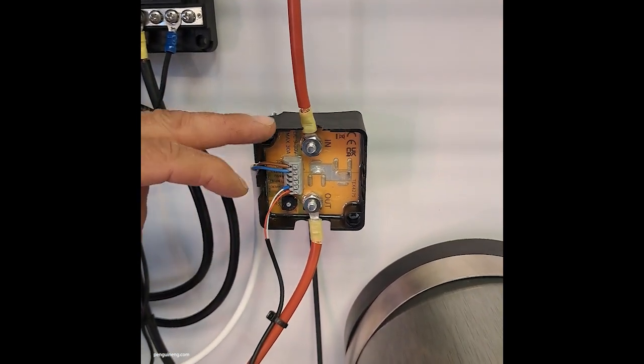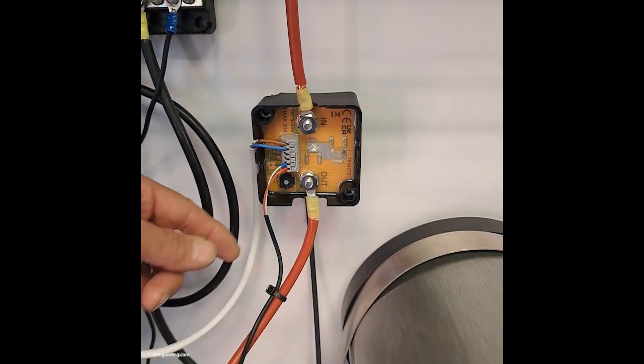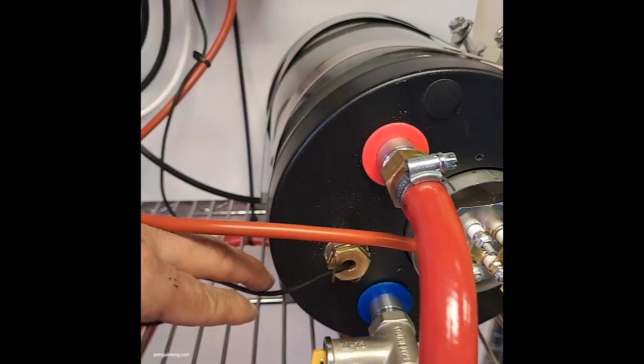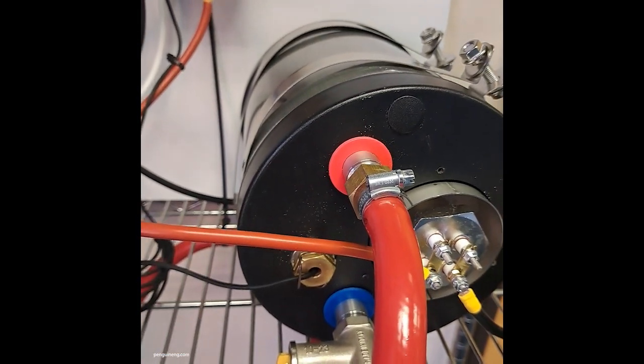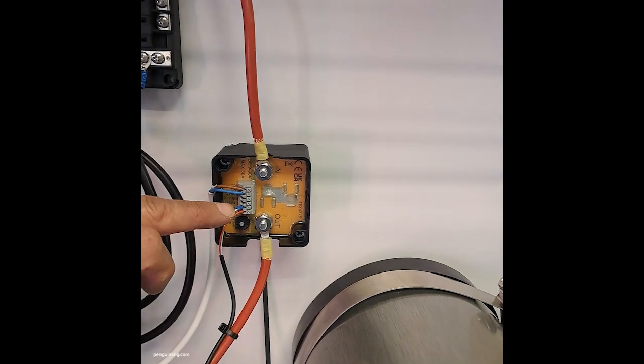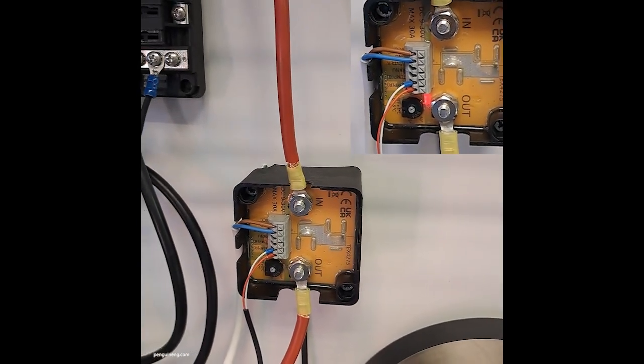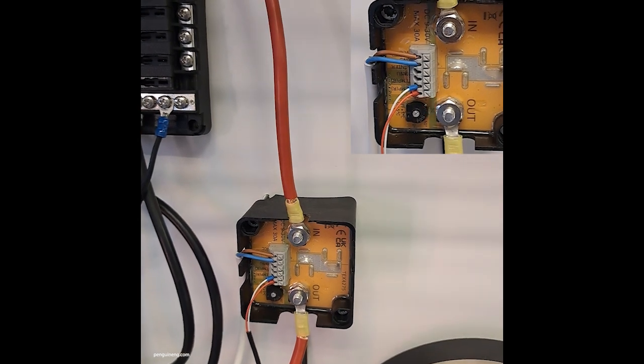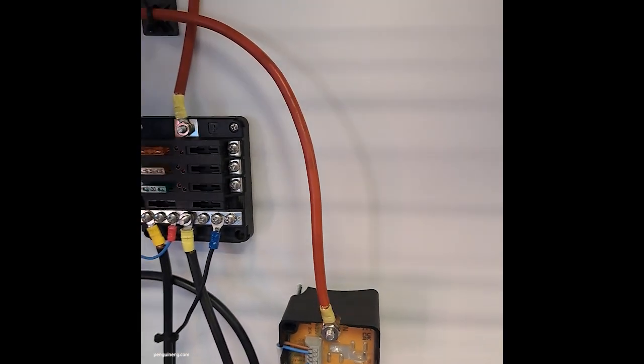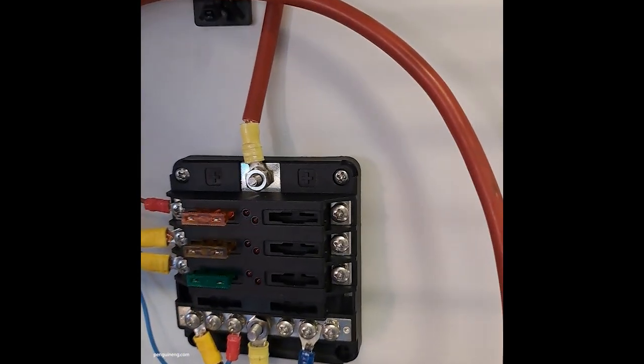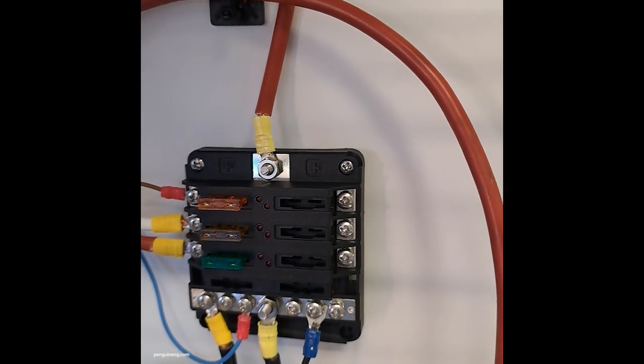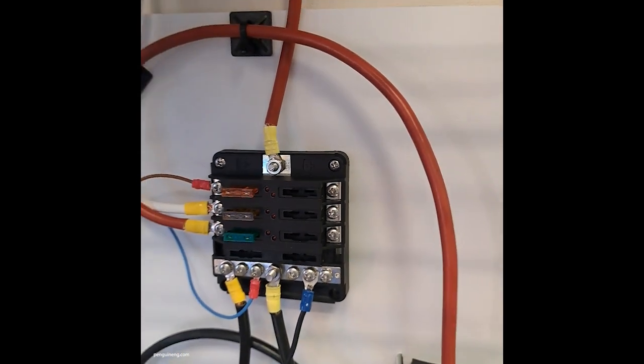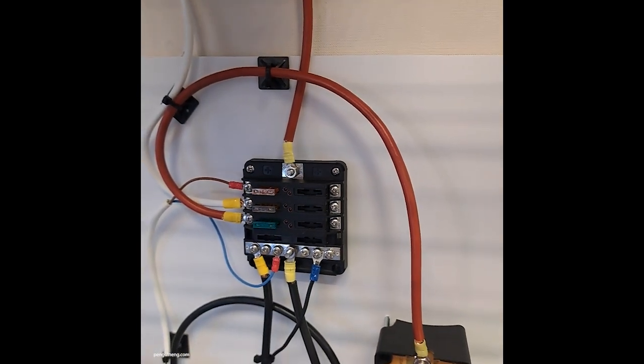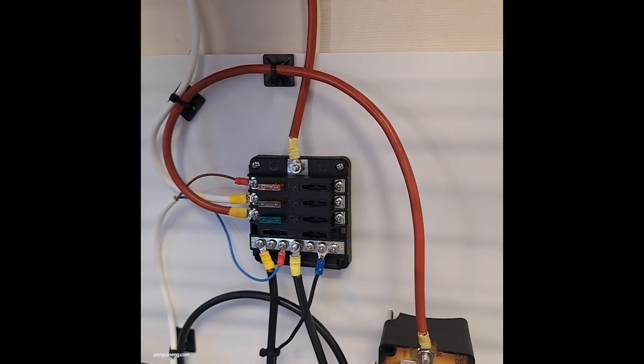The positive is then controlled here within the control system by this temperature sensing probe. The red temperature light on the controller will glow red when the boiler is heating up and will go out when the correct temperature has been reached. The other wiring here is for the pump, which has a 5 amp fuse, and for the control system, which has a 1 amp fuse. Again, make sure the fuses that you use are correct for your own installation.